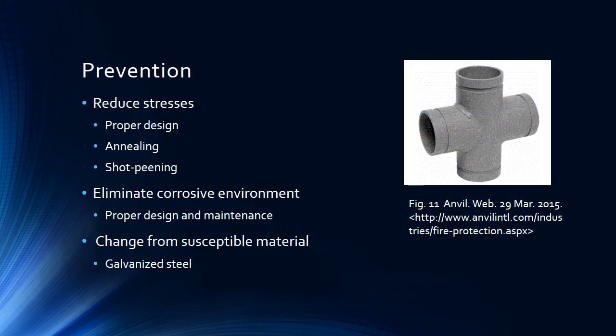There are multiple ways that environmentally assisted cracking in fire sprinkler systems can be eliminated. One is to reduce the stresses, and that can be done a number of ways. First, through proper design. Secondly, annealing or heat treating the pipe. Third, by introducing a compressive stress along the surface of the pipe through shot peening.